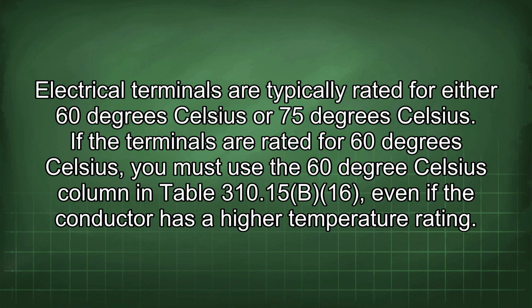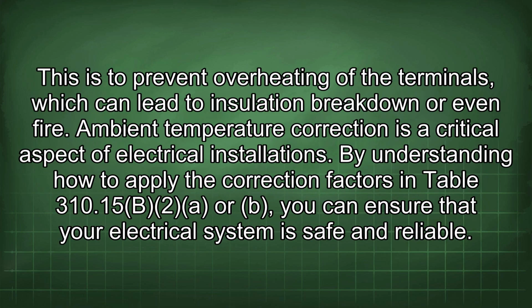If the terminals are rated for 60 degrees Celsius, you must use the 60 degrees Celsius column in Table 310.15(B)(16), even if the conductor has a high temperature rating. This is to prevent overheating of the terminals, which can lead to insulation breakdown or even fire.